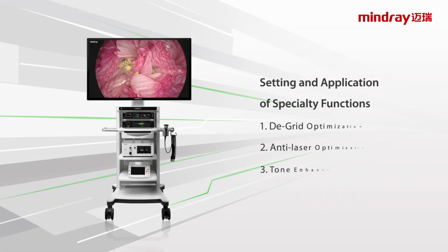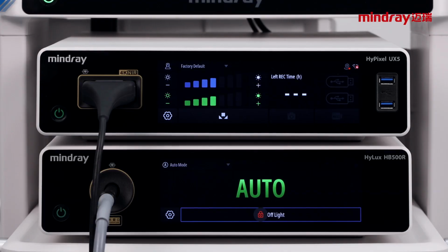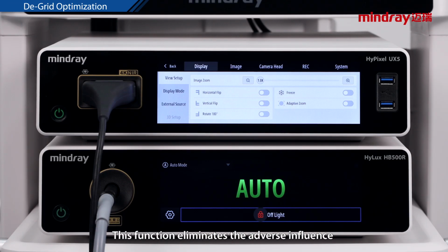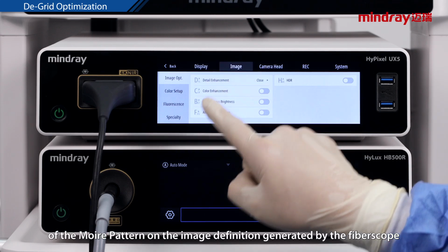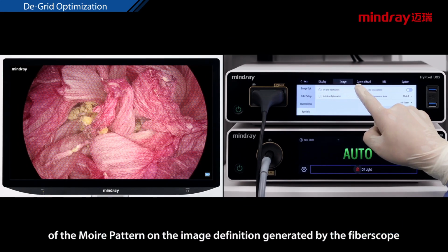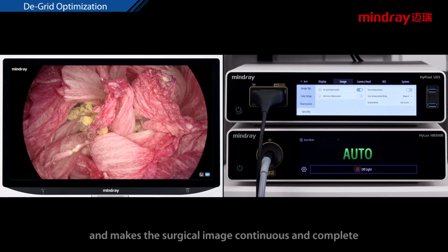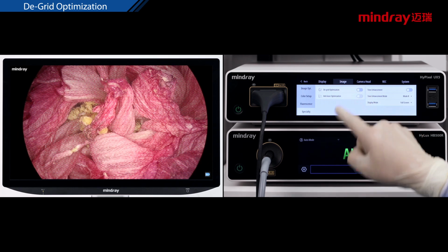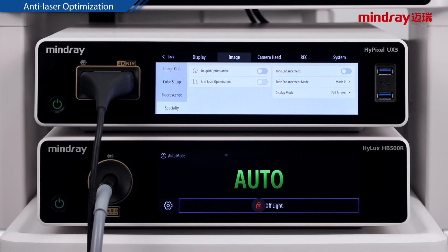Setting and application of specialty functions. De-grid optimization. This function eliminates the adverse influence of the moire pattern on the image definition generated by the fiberscope and makes the surgical image continuous and complete. Anti-laser optimization. This function can reduce the interference of the laser on the surgical image and ensure the image definition.